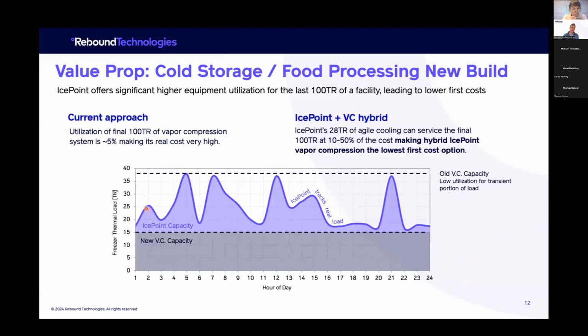With agile cooling, if this curve represents your facility load, serving the base load capacity with ammonia vapor compression or CO2 vapor compression is really cost effective. But serving the transient portion is not very cost effective, because you have to size your vapor compression system very large and then use it at a very low utilization. So you can use IcePoint to track the transient portions of the load, and vapor compression to serve the base load. Think of it like a peaker plant and a base load plant in electrical generation. What that does is yield a hybrid system that has the lowest first cost.